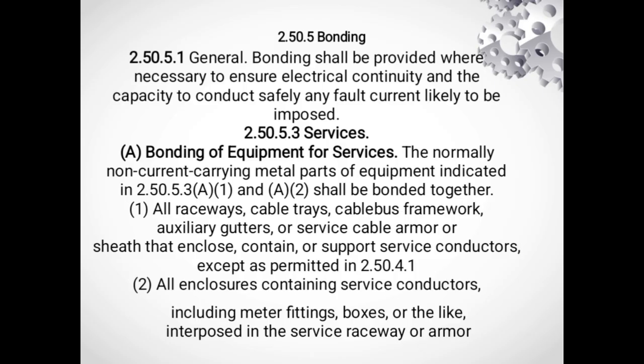Now let's transition to section 2.50.5, which deals with bonding, and 2.50.5.3 Services. Section 2.50.5.1 establishes the general principle of bonding, ensuring electrical continuity and the capacity to safely conduct any fault current likely to be imposed. Section 2.50.5.3 specifically mandates bonding of all metal parts of service equipment. This is paramount for creating a low impedance ground fault current path. Effective bonding minimizes touch potential during a fault, reducing risk of electrical shock.